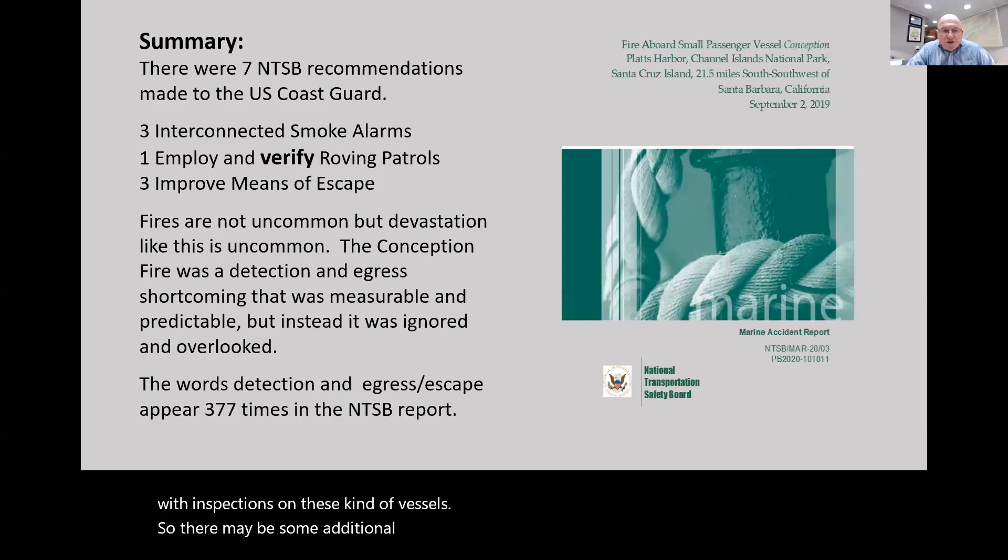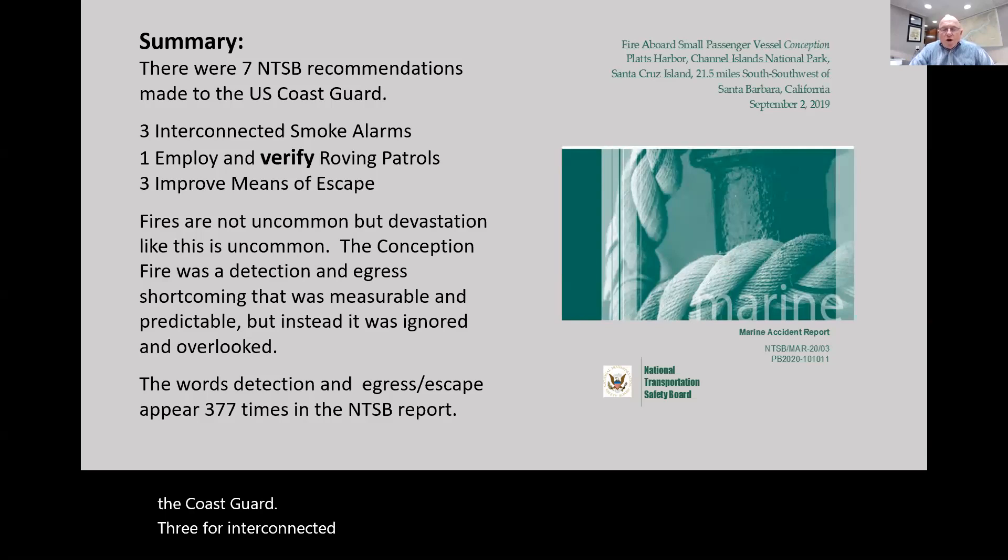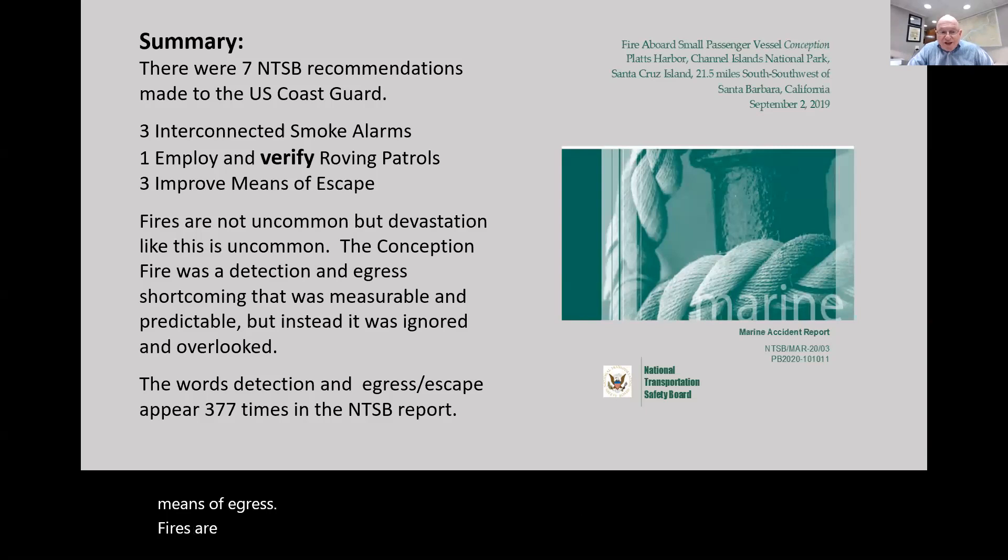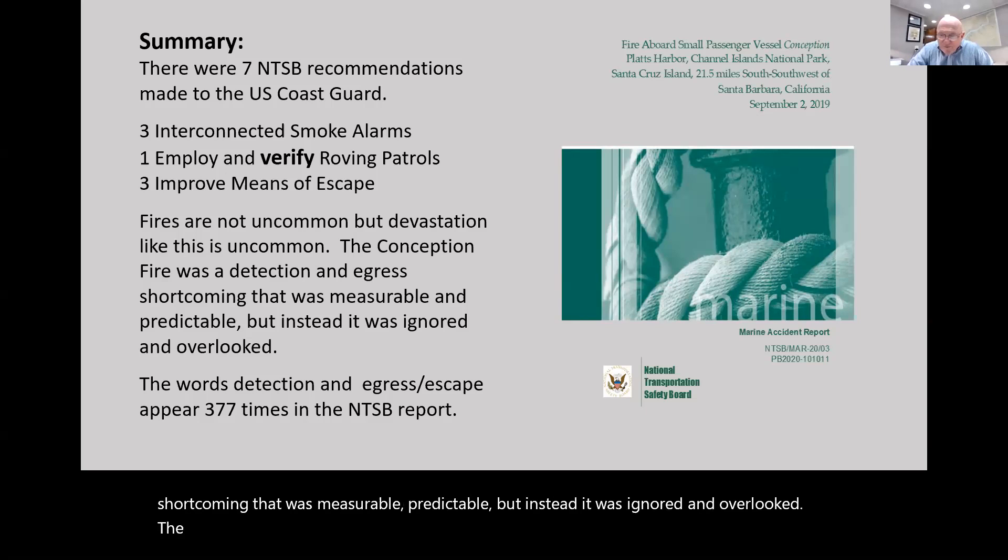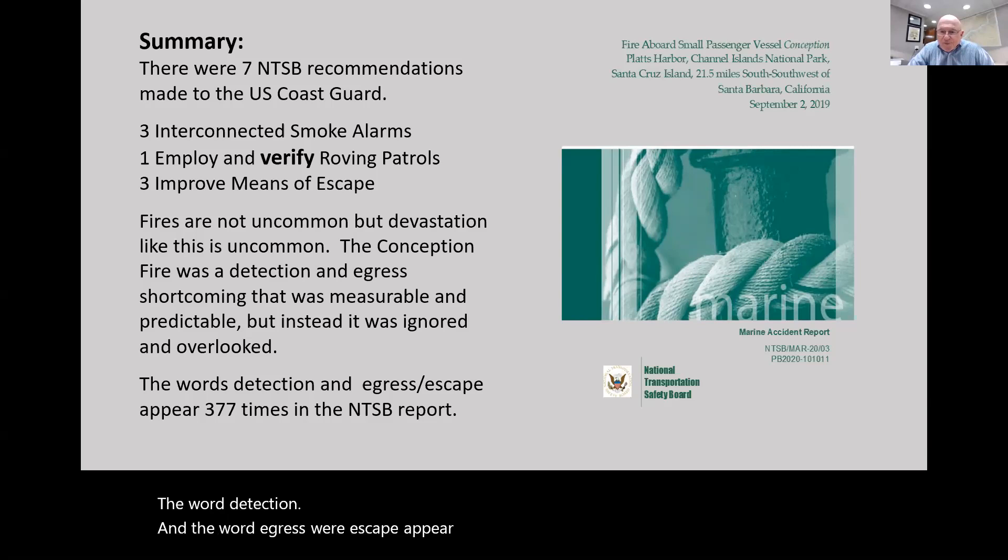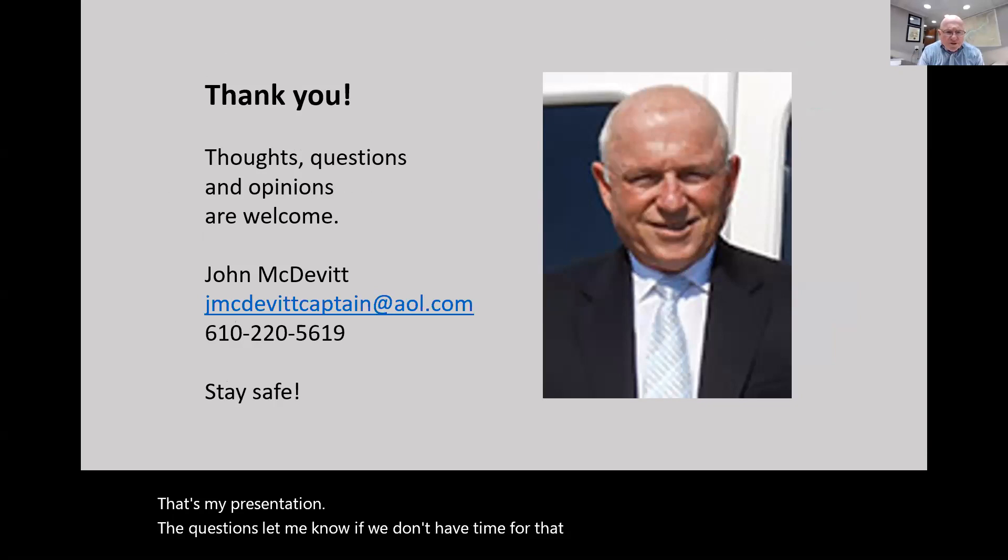In summary, there were seven National Transportation Safety Board recommendations made to the Coast Guard: three for interconnected smoke alarms, one for the roving patrol, and three more to improve the means of egress. Fires are not uncommon, but devastation like this is uncommon. The Conception fire was a detection and egress shortcoming that was measurable, predictable, but instead was ignored and overlooked. The words detection and egress or escape appear in the NTSB document 377 times.